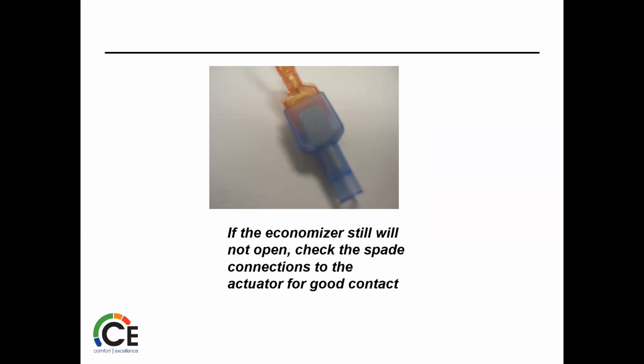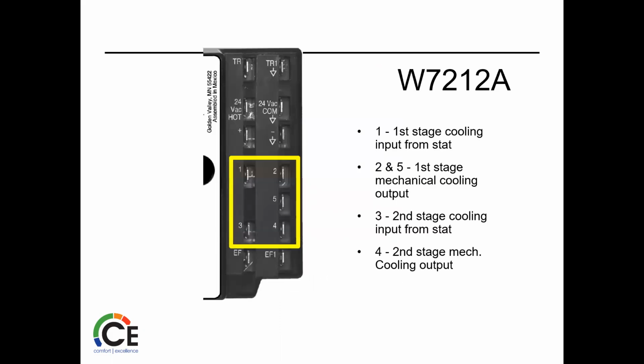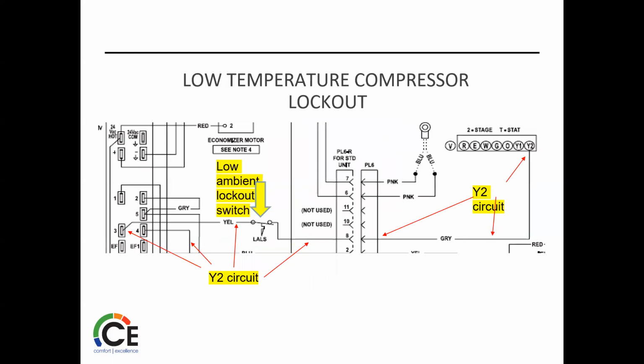Testing wise, if the economizer still won't open or you have some issues, check your connections. There's obviously one that from a distance probably looks like it's connected, but it's not. The female and the male are definitely not together. So silly things, but hey, make sure it's in there. I talked about how the right side is your first stage cooling input, first stage mechanical cooling output. So we're in and out, just like we talked about on the board. Now the signal's coming in, and we're going back out of the economizer to the board. And there's just another version of that.